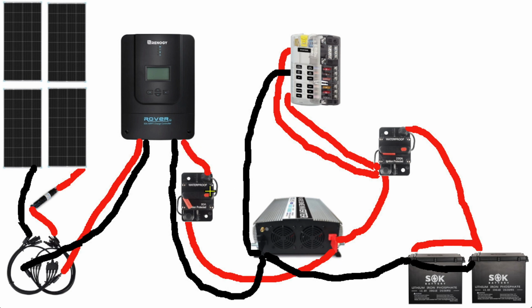The first circuit breaker is connected here, based off the solar charge controller. This is 60 amps, so we need at least a 60 amp circuit breaker. But we multiply that 60 amps by 1.25 for a margin of safety, giving us 75, so we actually used an 80 amp circuit breaker here.